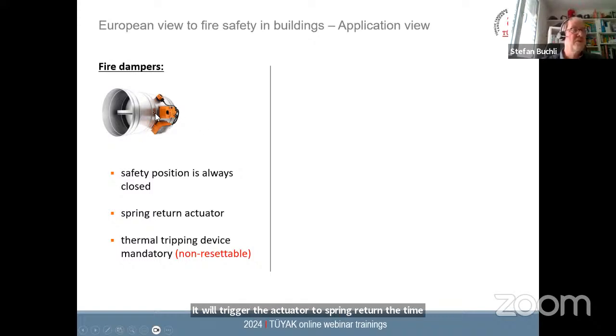But of course, if you have a more intelligent building, your fire alarm system triggers the actuator through the smoke detection system. It's also very important to note this thermal tripping device here. It's mandatory by the regulation, and it must be of a non-resettable type. It's not allowed to use a resettable type of thermal fuse.